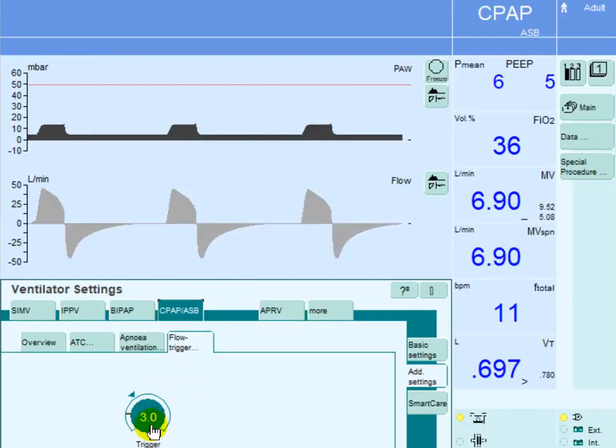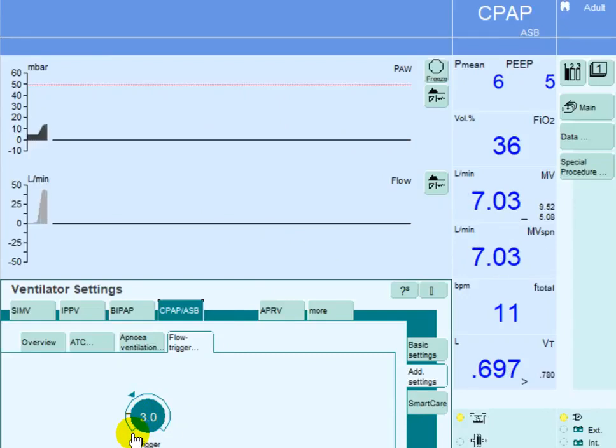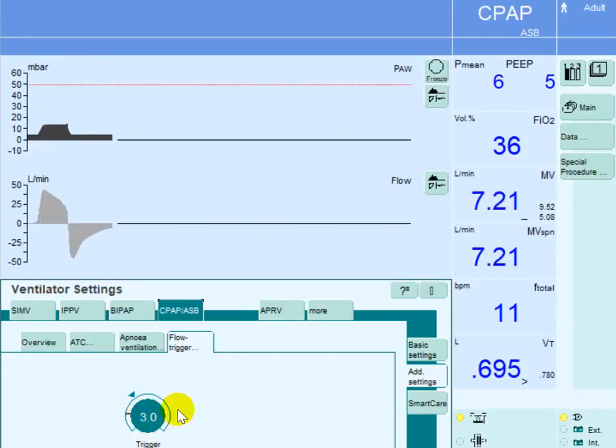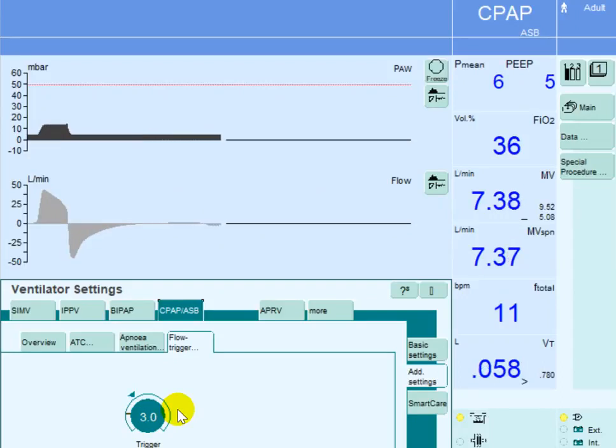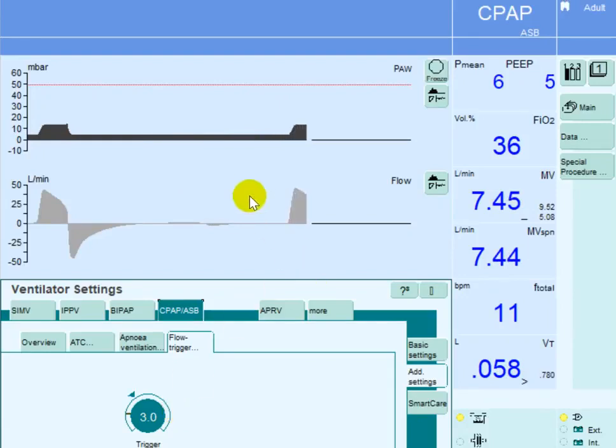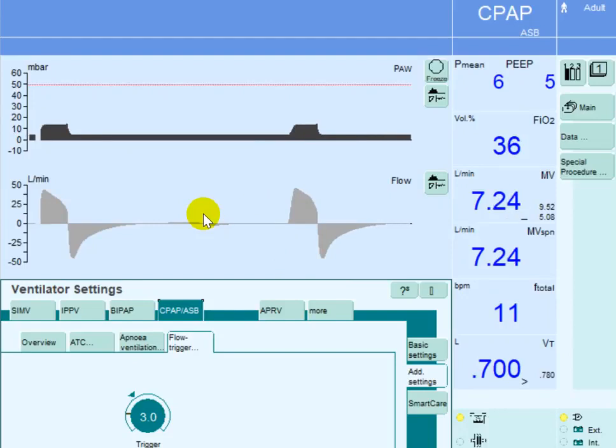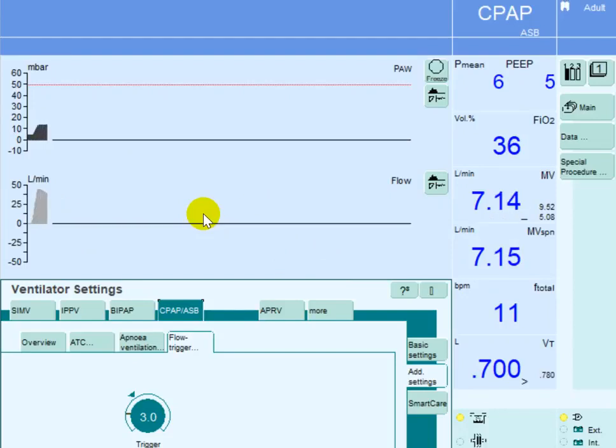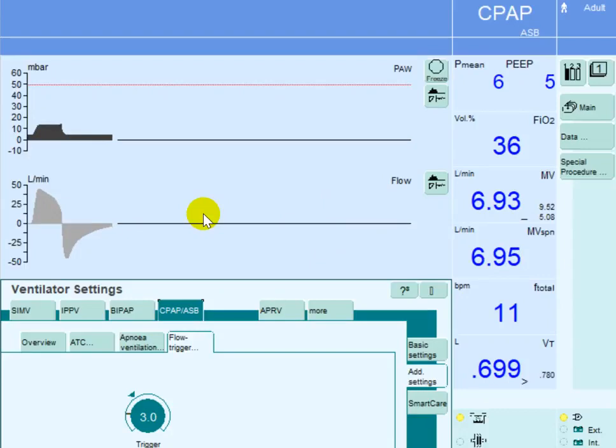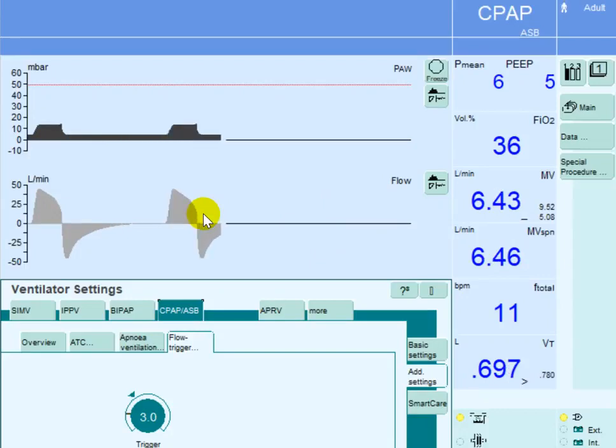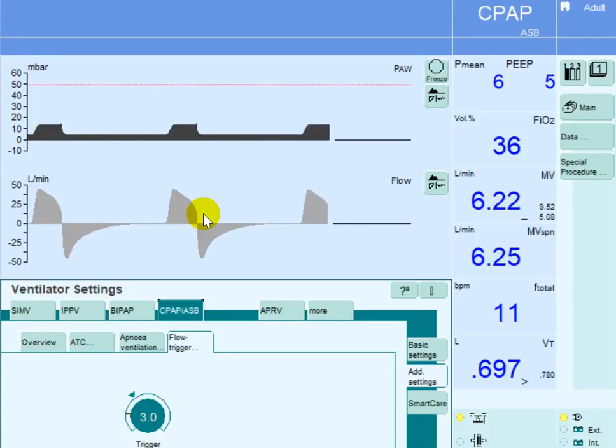You don't need to set this value very low. If it is set at very low value, any patient's movement or any air movement will result in triggering of the ventilator. This could be physicians listening to the chest or a nurse moving the patient to one side. Any inspiratory or expiratory flow, the machine will detect it as a flow change and it will be triggered with the inspiratory breath. Thank you.